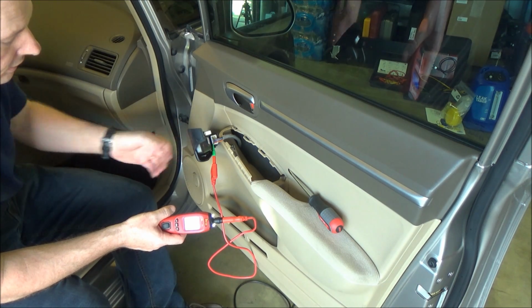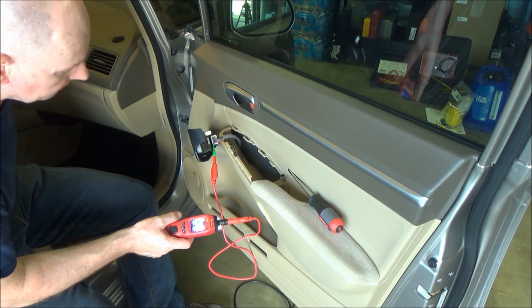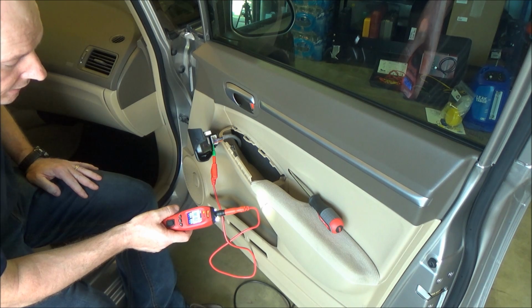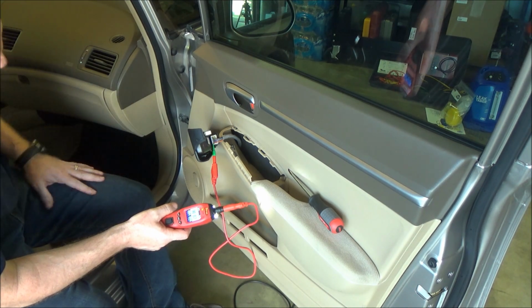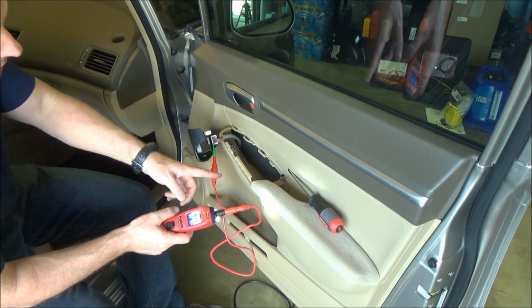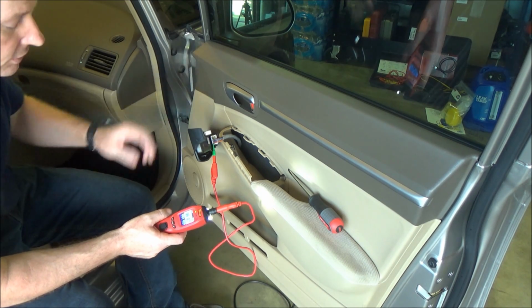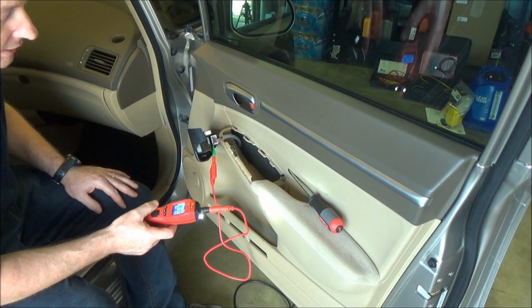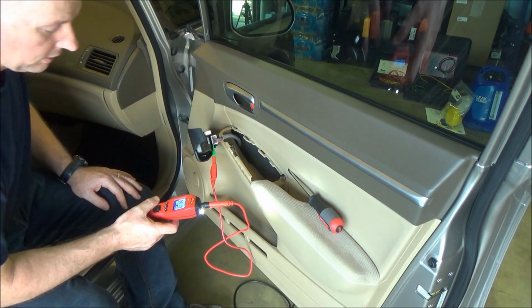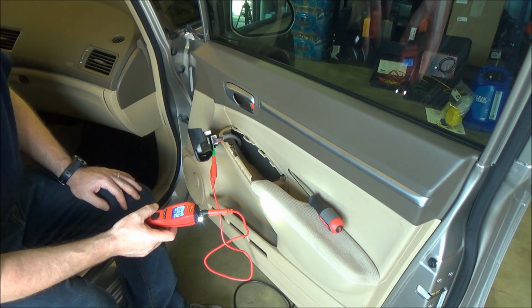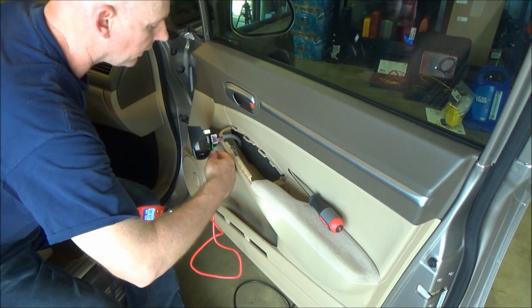It tells us our switches are good, and looks like all our wiring is probably good. We need to find out why we have those voltage drops. Most likely the motor is bad, but we need to make sure it's not a wiring issue. So now we'll have to go right to the motor itself and check it right there.